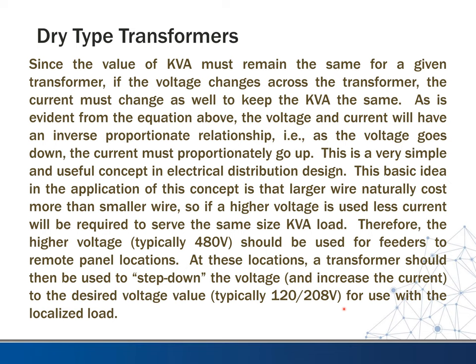So with the voltage staying the same, as the KVA goes up, the current must go up, or if KVA goes down, the current must go down across the transformer. So as evident from the equation above, the voltage and current will have an inverse proportionate relationship, i.e. as the voltage goes down, the current must proportionately go up. This is a very simple and useful concept in electrical distribution design.